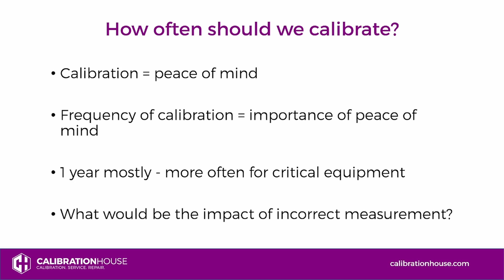Another question that people ask is, how often should we calibrate? There is no strict answer to this question. Calibration is the equivalent of peace of mind. Is my device accurate? The frequency of your calibration is how important that peace of mind is. The most common choice is 1 year. Some customers will choose to have their equipment calibrated more often if it's considered critical. You have to think, what would be the impact of incorrect measurement for a quarter, for 6 months? What impact would that have on your company, your customers, your products? And that's how you decide how often you should calibrate.